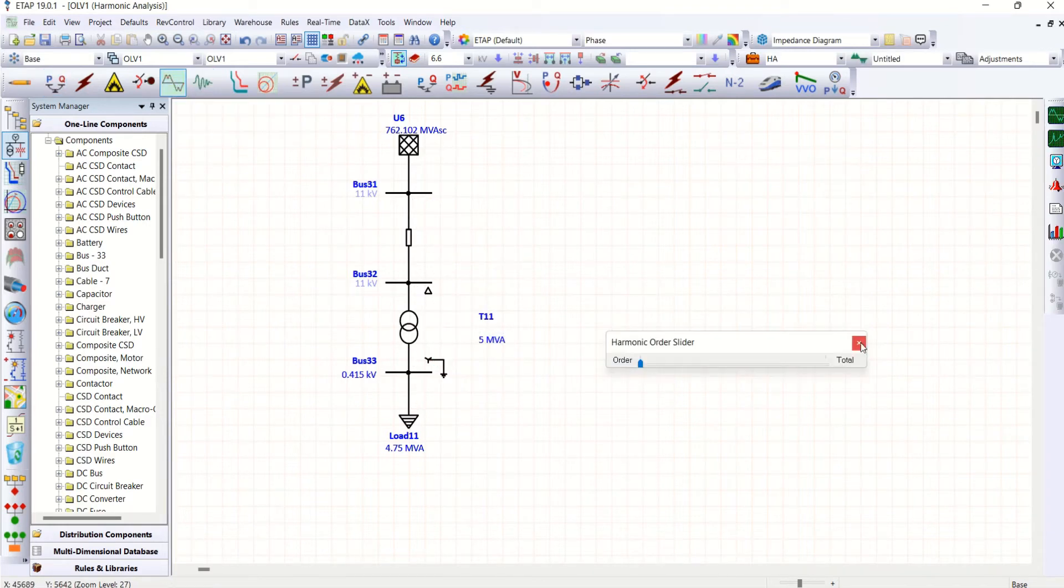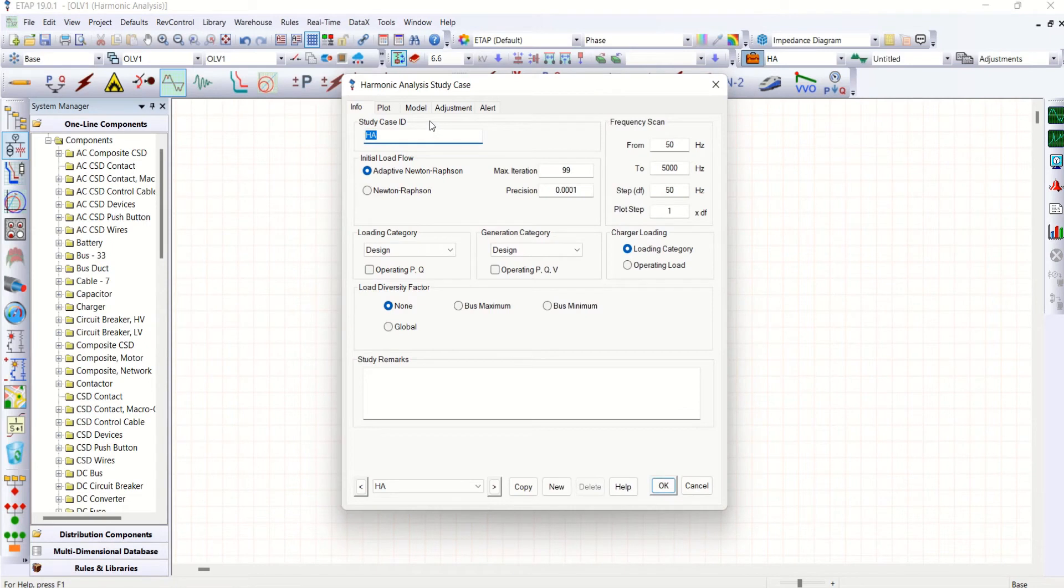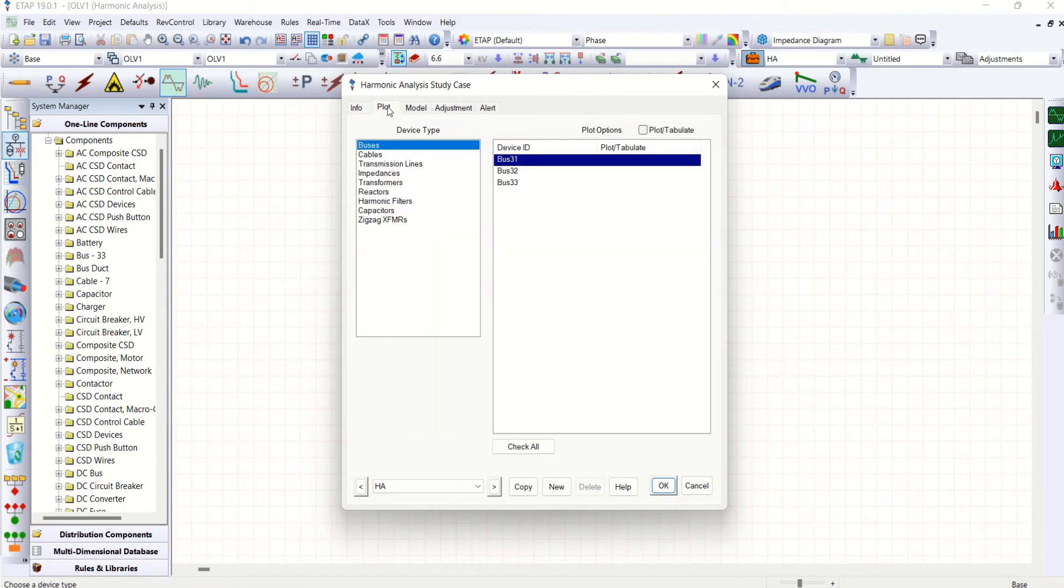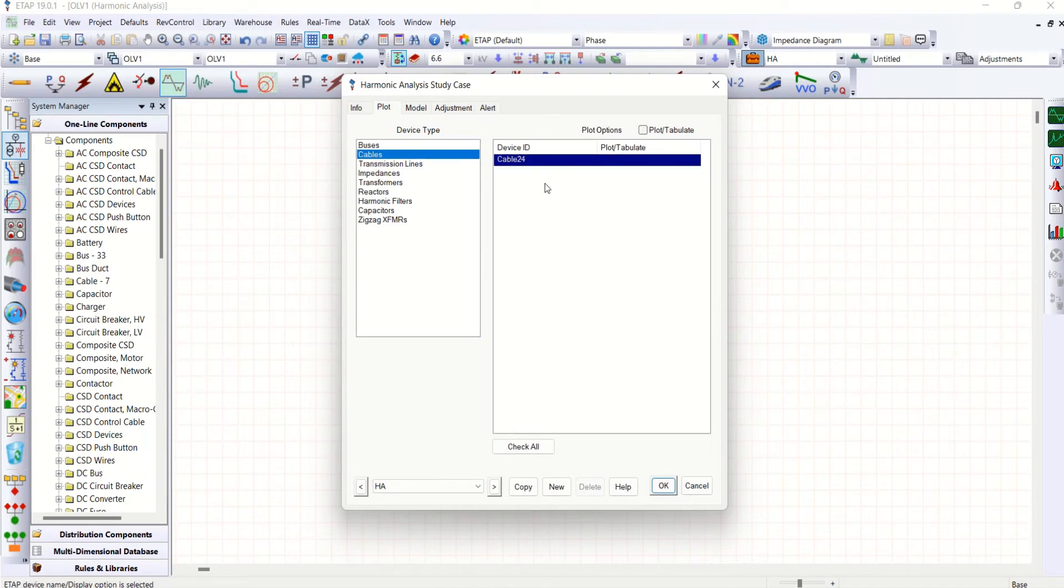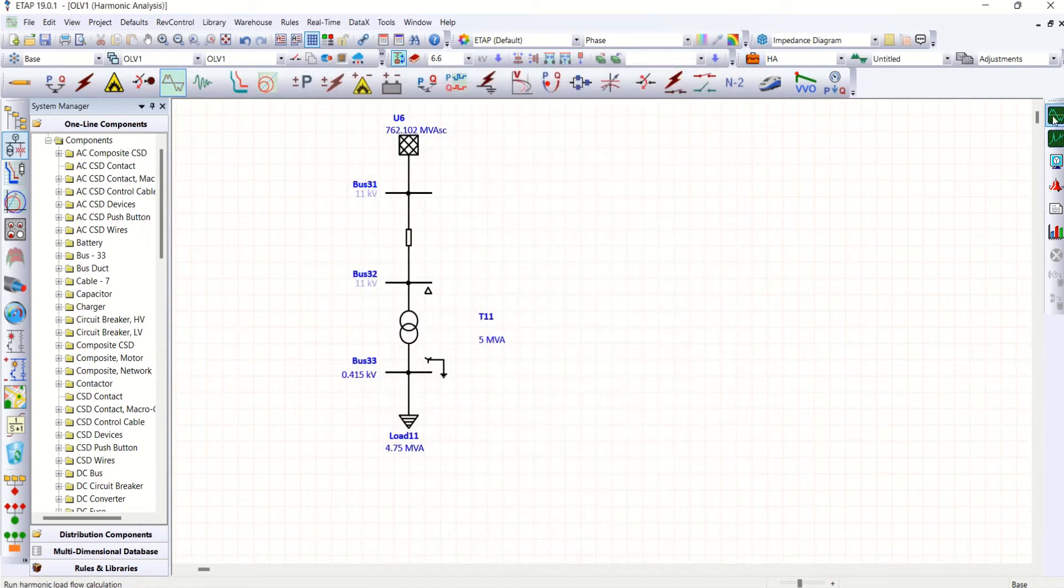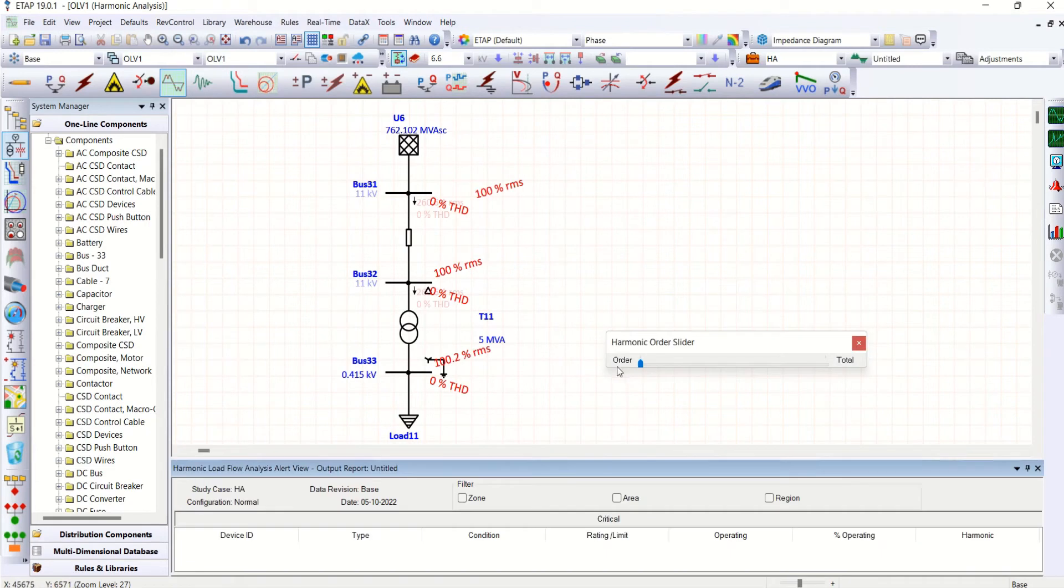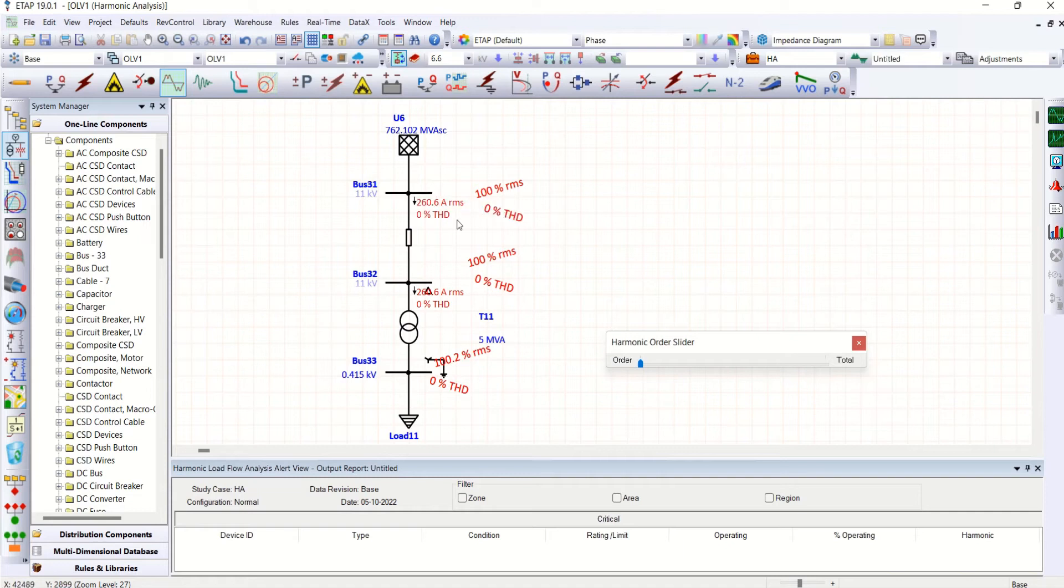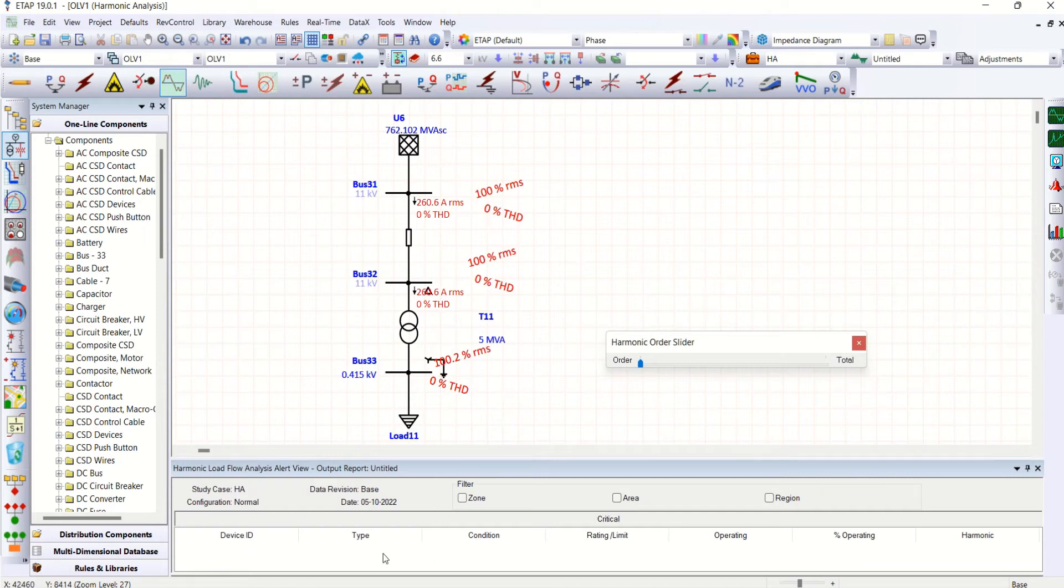Let me go to that. I have to plot here. So plot all buses and cables even transformers. Now run harmonic load flow. As you can see that everywhere 0 THD. This is because of no harmonics added or injected in any part of the system. Also you can see nothing is overloaded.